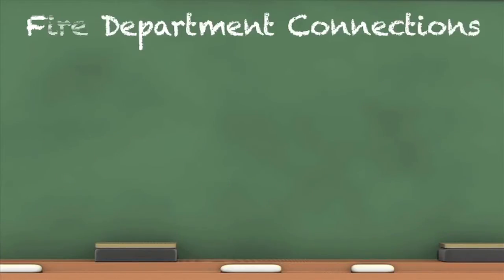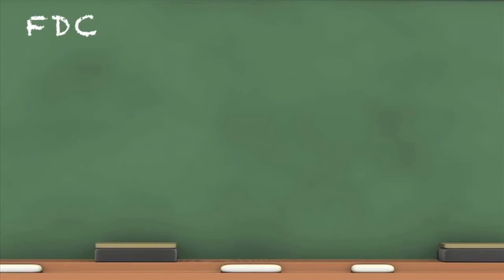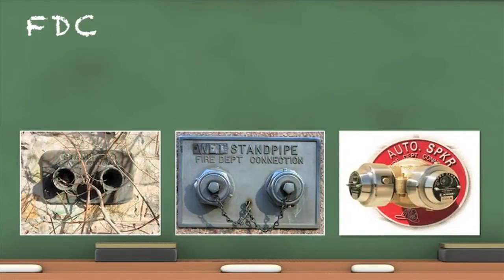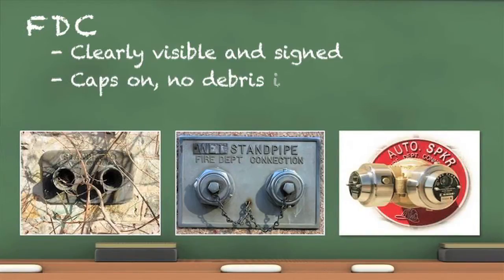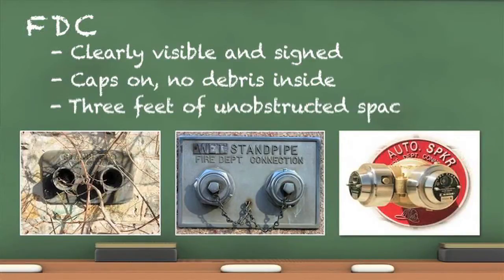Fire department connections (FDCs) are inlets that allow the fire department to connect fire hose to the building and pump in water to boost the water pressure for sprinklers and provide water for firefighting. Signage near the FDC indicating the type of inlet is required. All FDCs must have caps in place and inlets free of debris. A minimum of 3 feet of clear space around FDCs is required, which allows quick access for the fire department. The collar indicating the type of connection must be in place and legible.